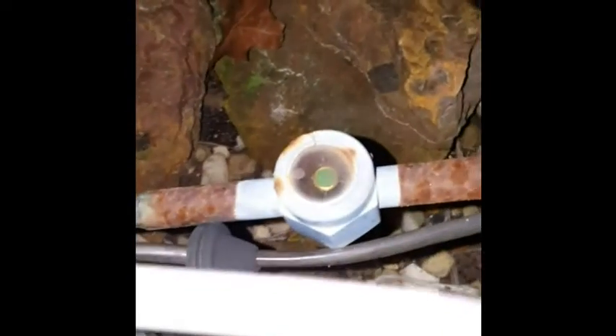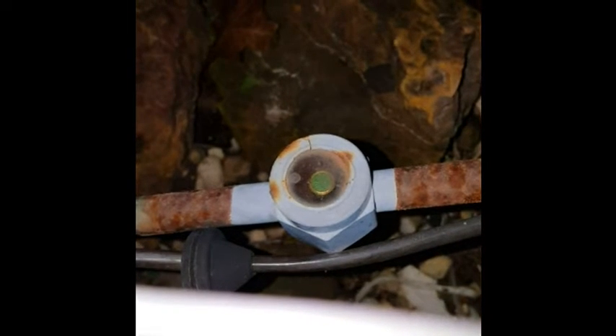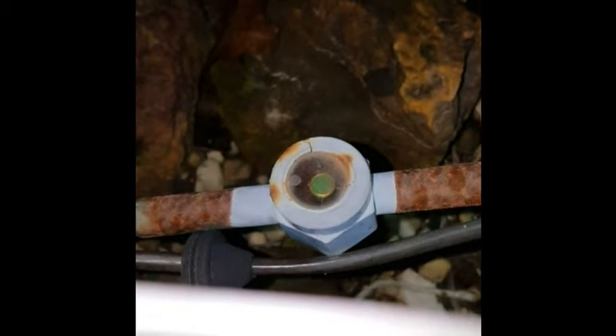You can also do your subcooling check here — we've got a nice little sight glass. From the sight glass you can see we have low subcooling. But if you didn't have a sight glass, throw a gauge on there and make sure your head pressure is not going crazy.